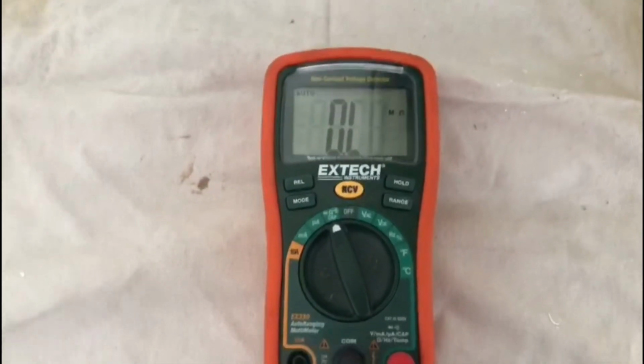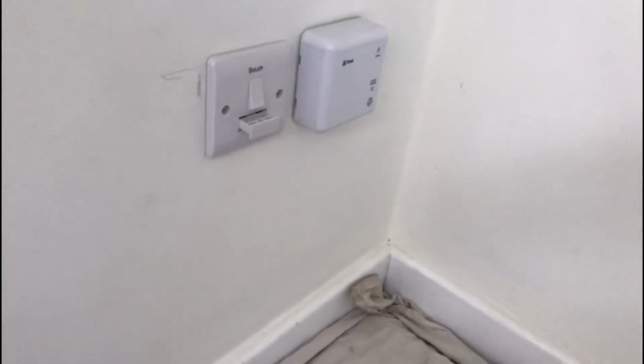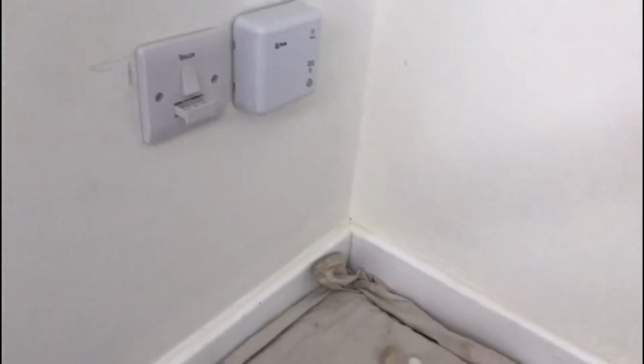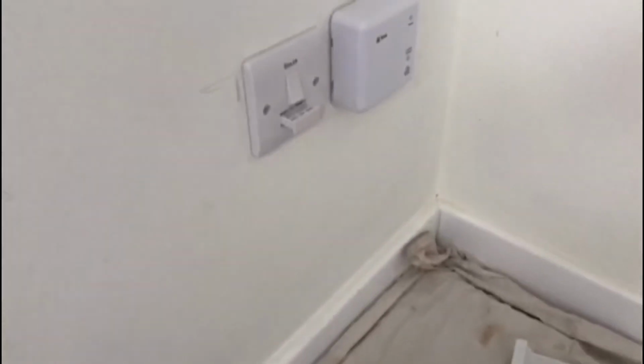Right, to test the earth continuity on this boiler, you need to go from the earthing bar of the boiler, which is just there. If you can see all the earth wires going to there, they're like a metal strip. That's the earthing bar of the boiler. Now the way that we test the earth is to test from the earthing bar to the earth pin on your fuse spur, because normally they are linked up and tested to the earth of your whole house system. So to put this into practice, we'll test from the earth pin of our fuse spur to the earthing bar of our boiler.